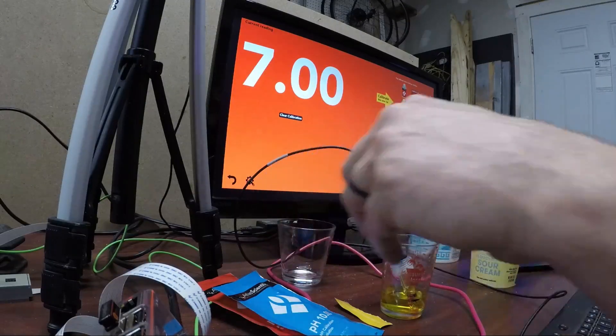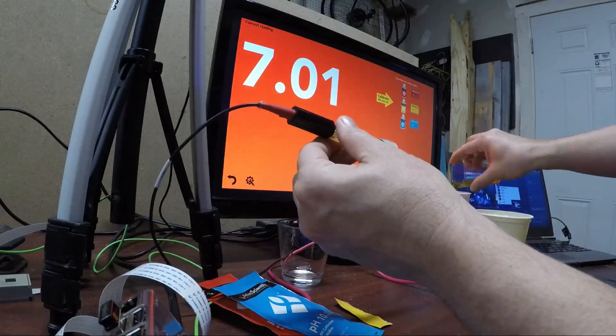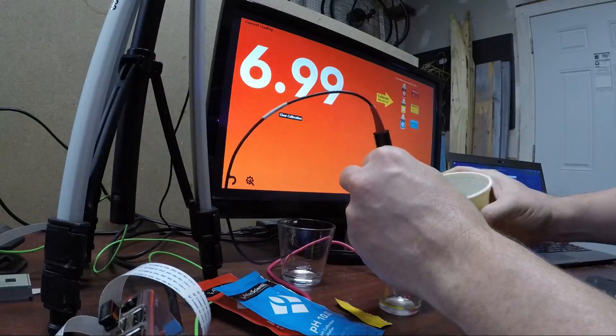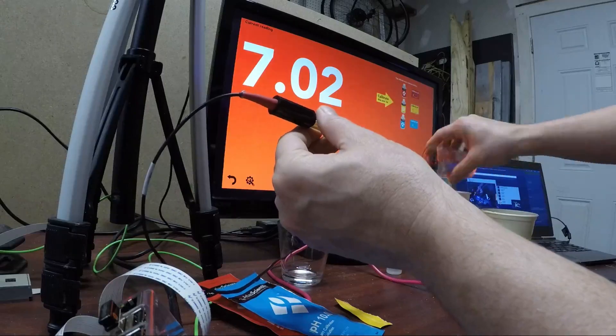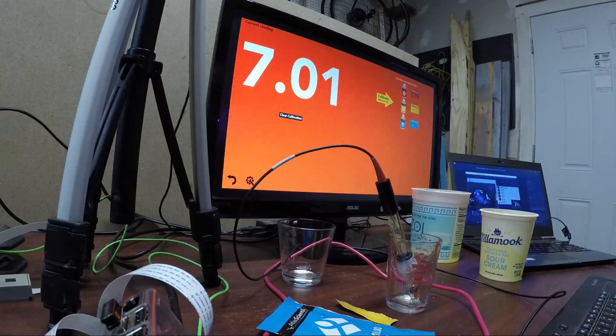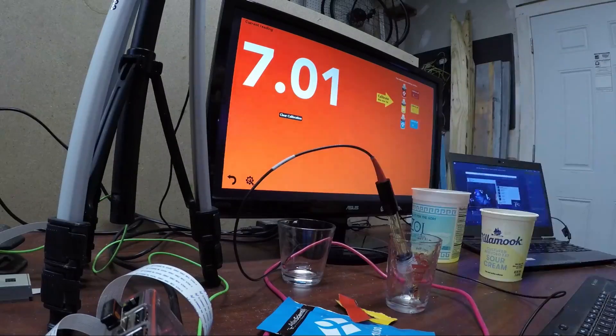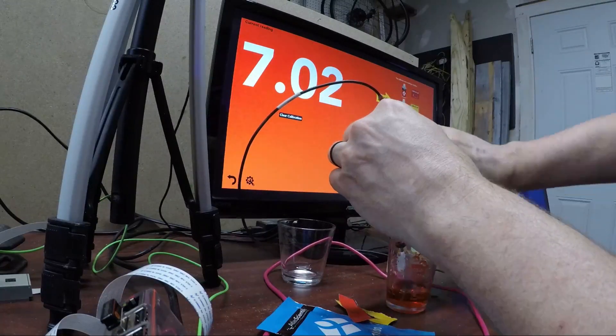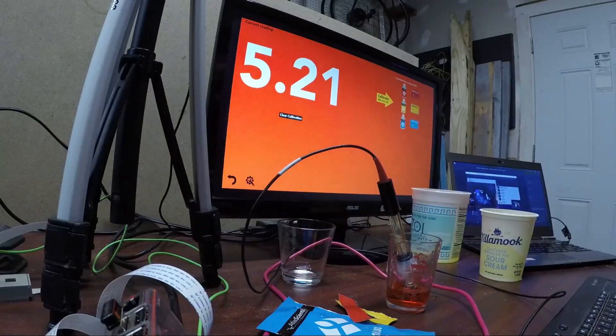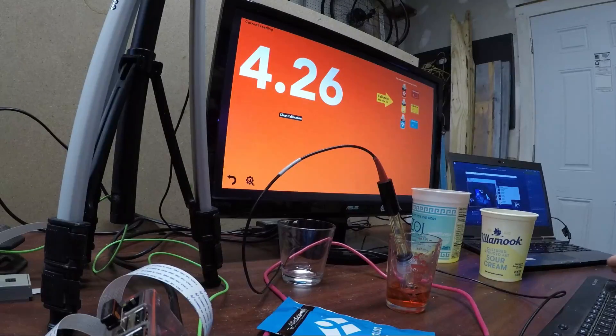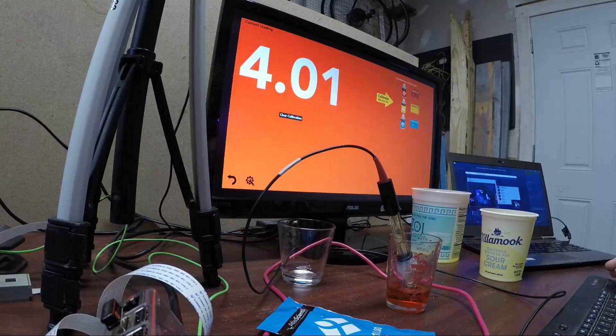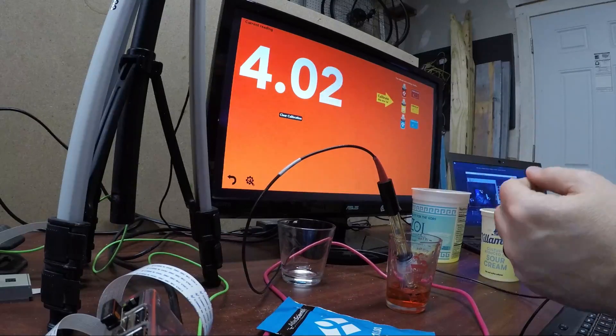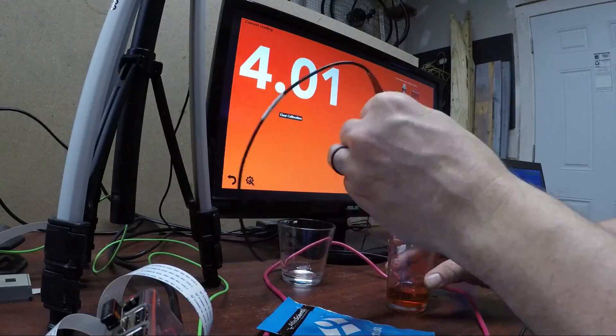But what we're going to do here is we're going to dump our solution out. Put a little water in here. We're going to clean that out. We'll dump that in there. Now we're going to do our base at four. We're looking pretty steady around four to five, so we're going to calibrate this at four. So it adjusts the sensor to say that this is around four, 3.98, 4.02. Next up.